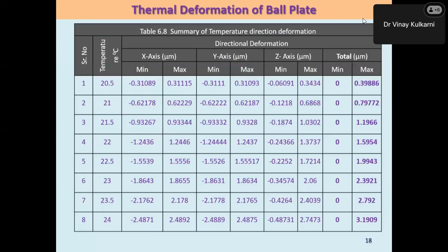And at the same time, we have made the calculations here: what will be the drift in the temperature in X, Y, and Z axis at 20.5, 21, 21.5, up to 24. We have taken this, and what is the drift that we have measured? As you can see, this is the total drift here, and that is up to 3 microns.